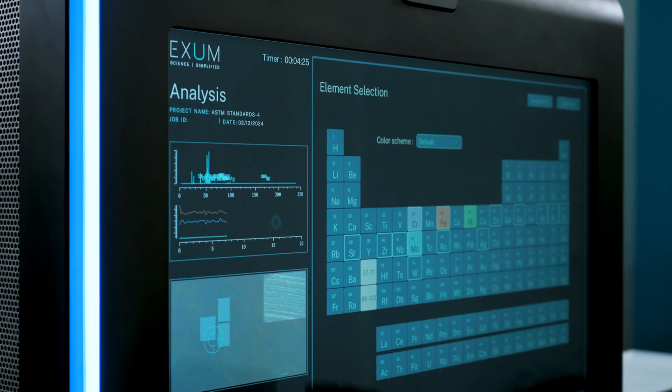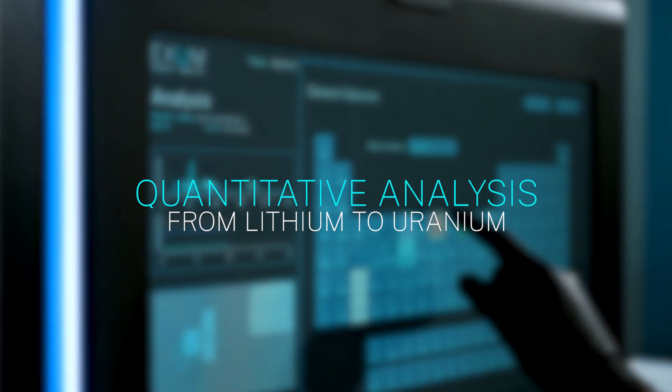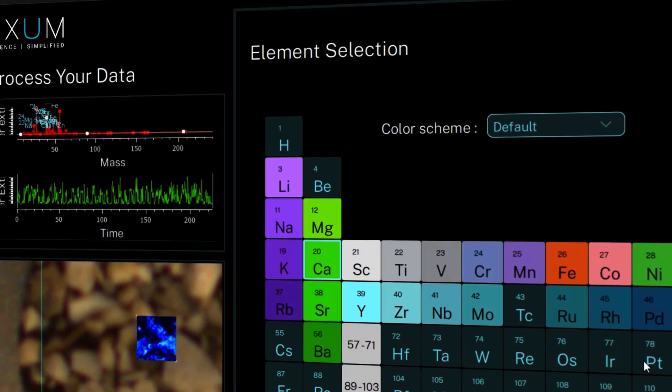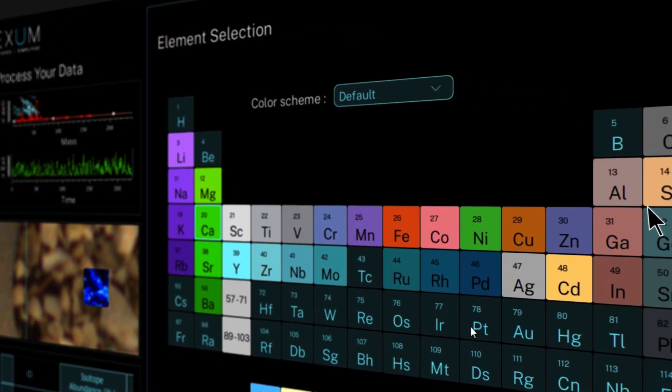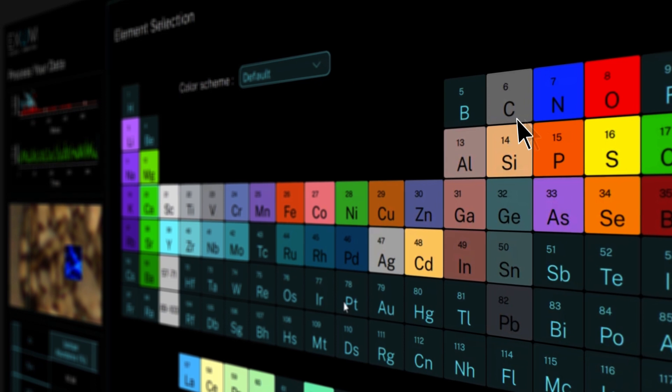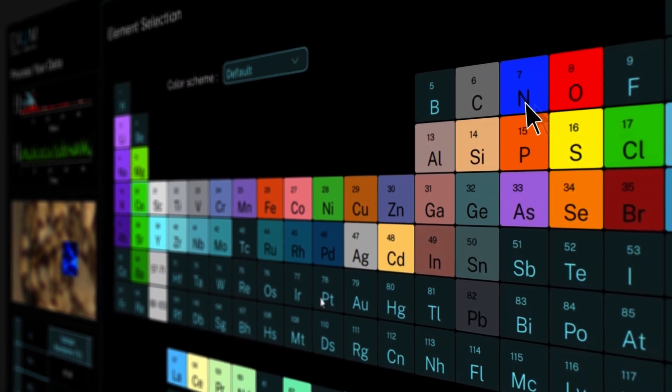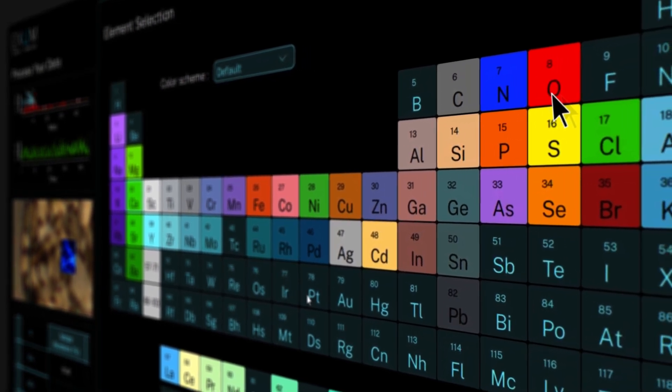We focus on four modalities with the MassBox. Specifically, we want to be able to do full periodic table quantitative analysis down to high parts per billion level limits of detection. You no longer need to go through three different instruments to get all of your elements. We analyze lithium to uranium, including the hard to get elements like carbon, nitrogen, and oxygen, and we're able to quantitate these with a high level of precision and accuracy.